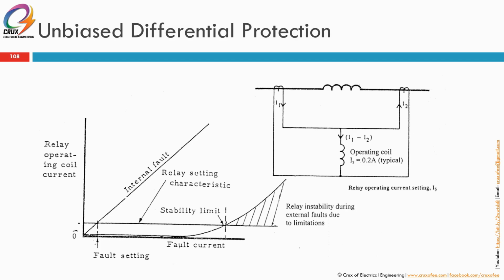So what to do is we will introduce biased differential protection. This is the normal unbiased differential protection. This is your equipment under protection, cable or transformer. The operating coil is typically set at 0.2 A of the CT secondary. This is typical, 0.2, 0.15.